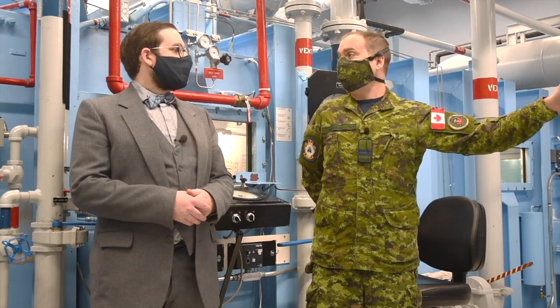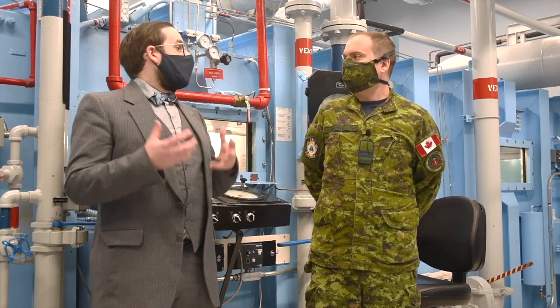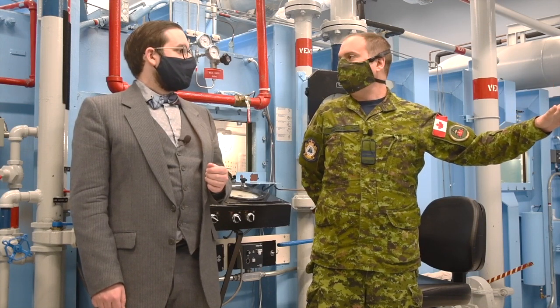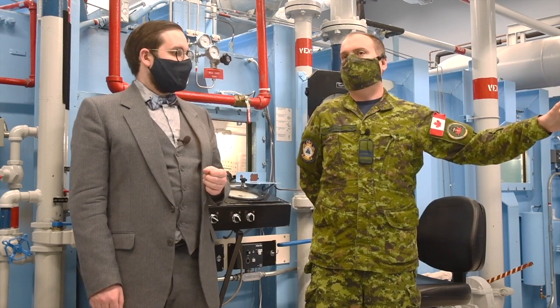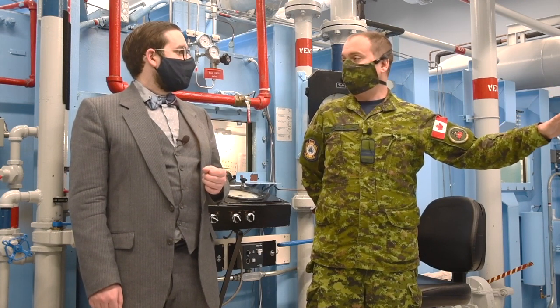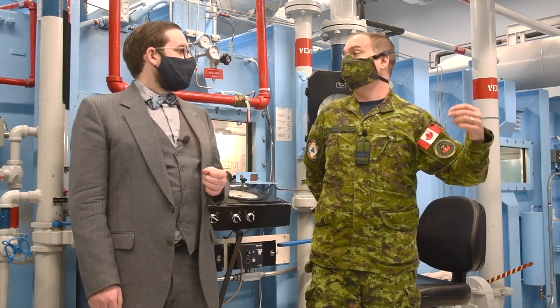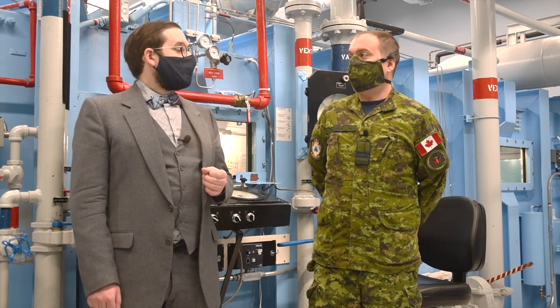This smaller chamber does have to go to 60,000 feet regularly to do the decompression — it just serves as a vacuum tank for the blowdown. Back in the day, and in Toronto, medical treatments have been done using hypobaric oxygen for smaller groups of people to see if they had problems with flying on civil aviation. That has been done in the past, but not at this location in the time I've been here.